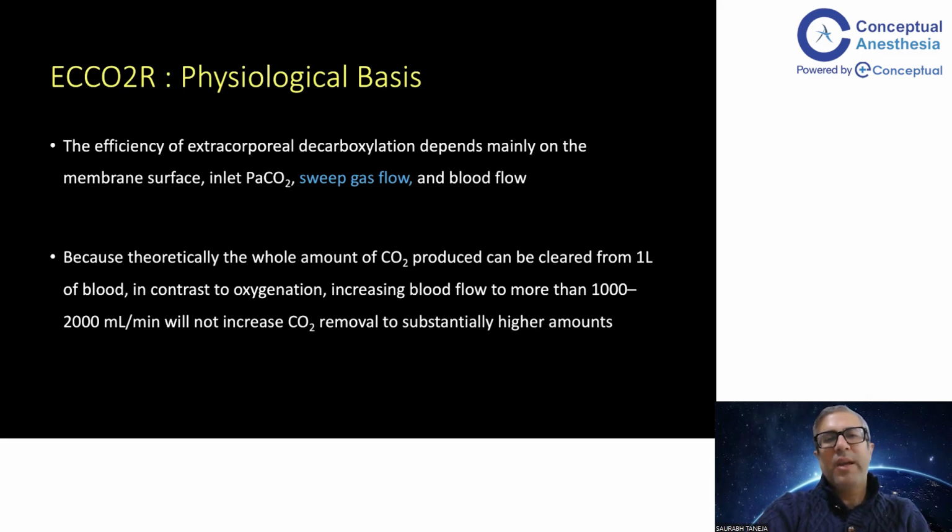Then we talk about sweep gas flow. Sweep gas flow is one of the major factors which tells you about the efficiency of CO2 removal. The higher the sweep gas flow, the higher the CO2 that is removed. The higher the blood flow, the higher the CO2 removal. But sweep gas flow is the most important thing amongst all these four.